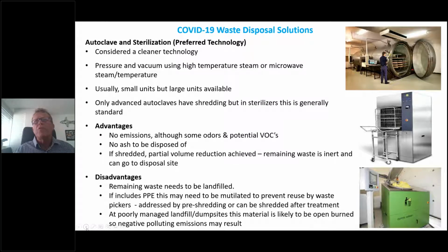You can usually get autoclaves in clinics, etc., as small units, and they're used for cleaning reusable equipment. But you can also get large units, such as the picture in the top right hand corner, which can be loaded on different levels with lots of bags of waste to be sterilized. In the bottom right hand corner, you've got sterilization units that tend to have shredding as part of the process. This will enable the volume of the material to be reduced somewhat, but this is not always the case, and sometimes after the material has been sterilized or made safe, the infection taken away, it can be shredded with a normal shredder thereafter.